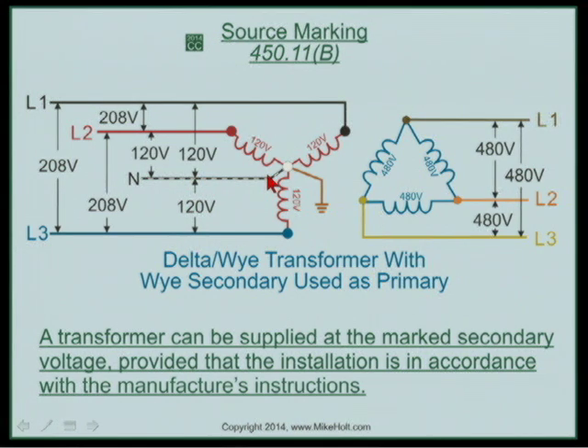Let me tell you when you do this. You are at a 120/208 system. You've got 277/480 volt lighting in the parking lot, and you want to connect the lights. So what do you do? You backfeed a transformer. Now you have an output of what? 480 volt ungrounded. What do we have to do when you have an ungrounded system? Got to put a ground detector.